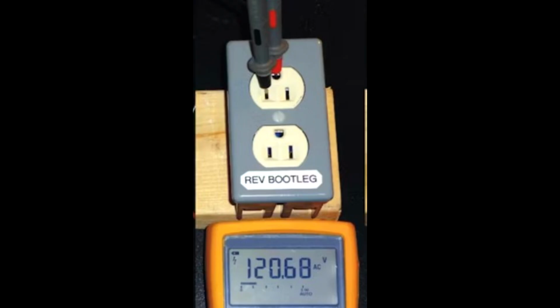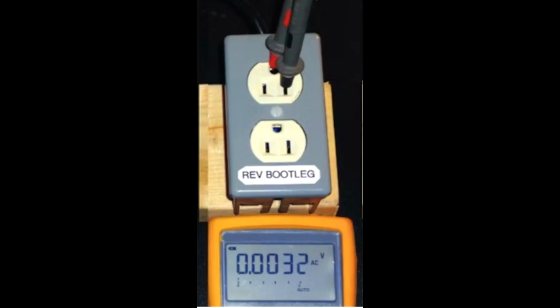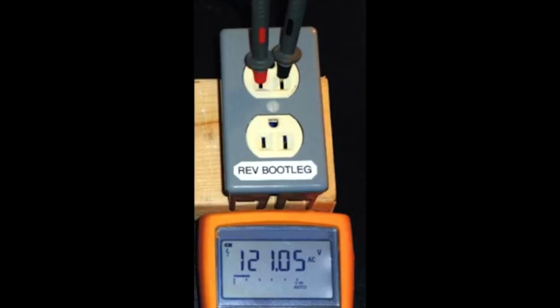This works because the ground and the neutral are bonded together at the main breaker panel. In this picture, the result is just a little bit of residual electric through the line. That's from testing the neutral to the ground, as they are connected. If you wanted, you could even run a continuity test on those two, and they should connect. And in this picture, you see the right way to do it, with the black lead into the neutral and the red lead into the hot.